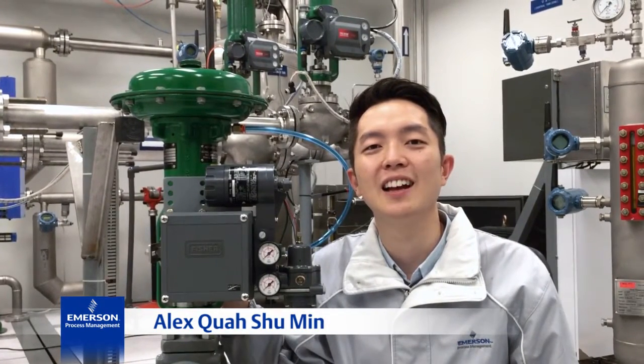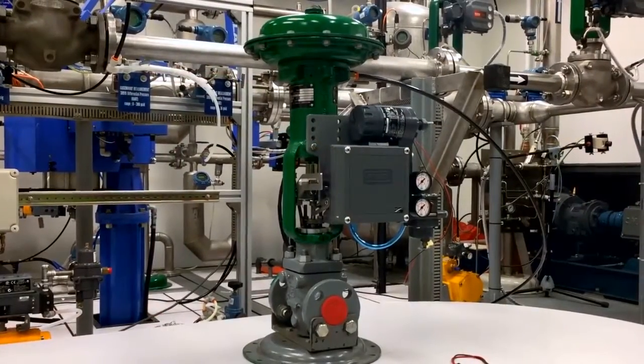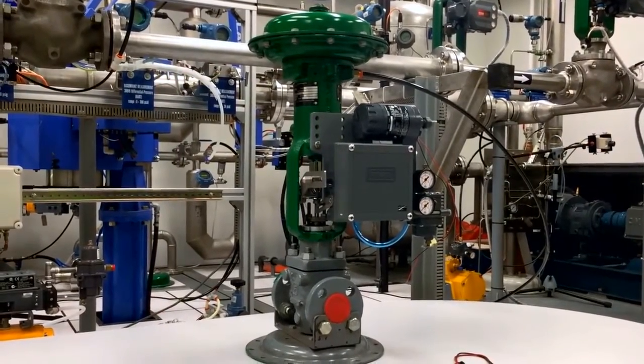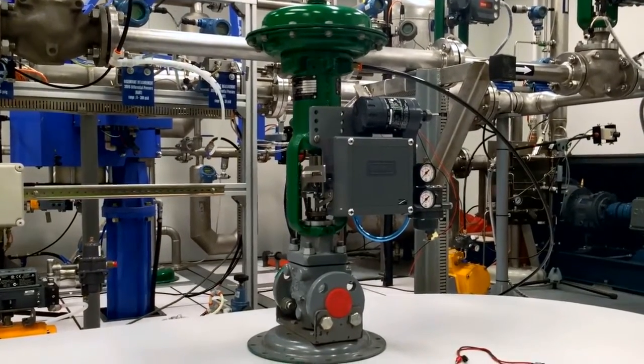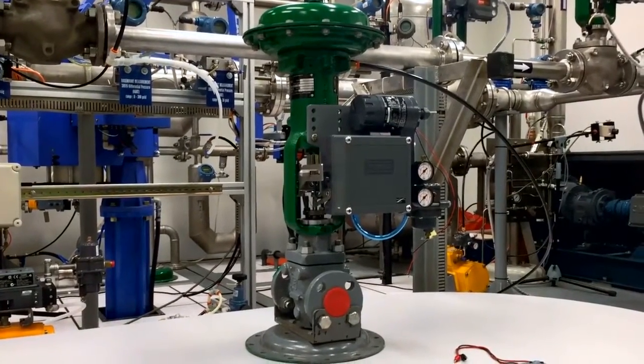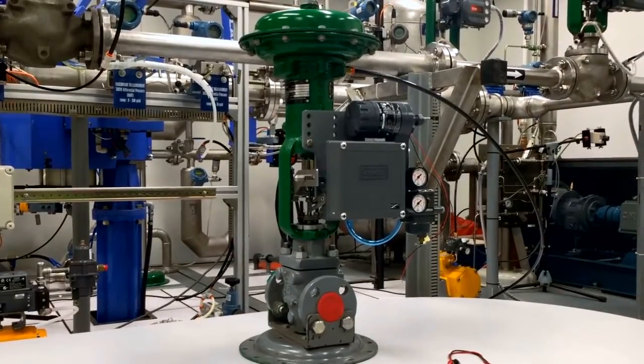Hi, my name is Alex and I'm a marketing engineer from Fisher. In this video we will be demonstrating the setup and calibration of the 3582i on a Fisher 667 size 30 actuator. The 3582i is an electric pneumatic valve positioner which takes a 4 to 20 input signal and positions the valve accordingly.